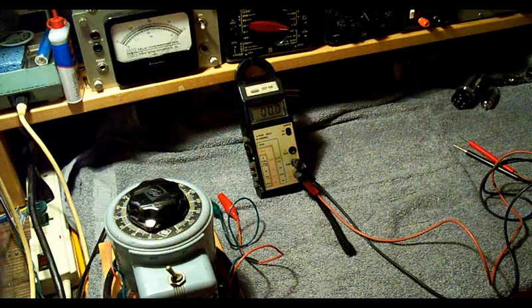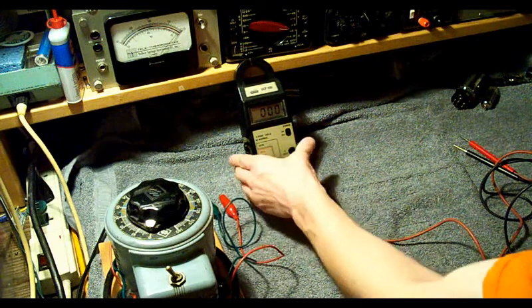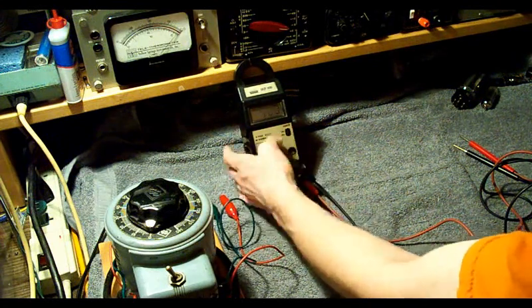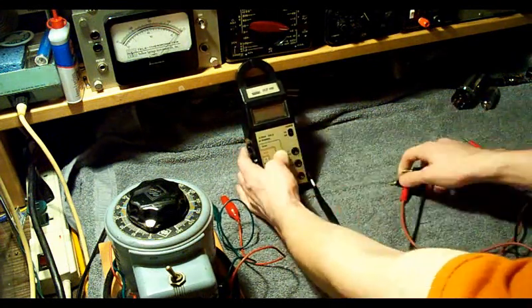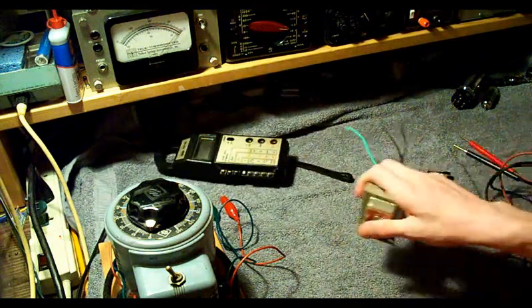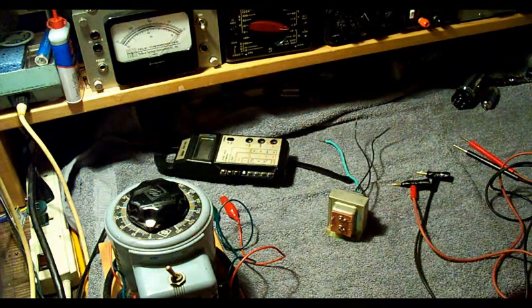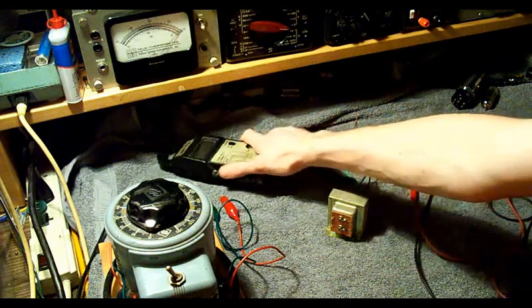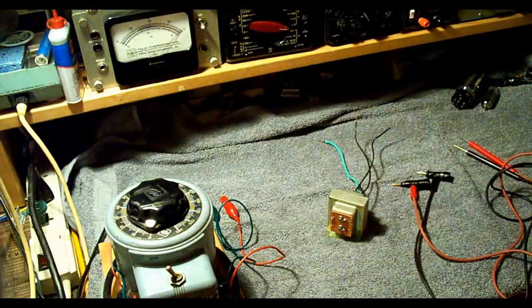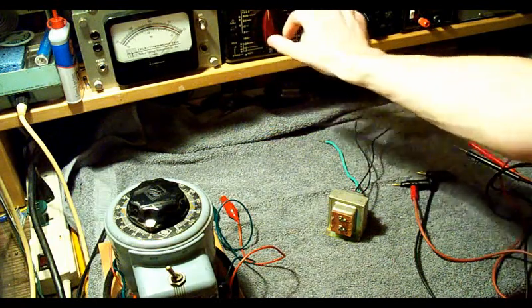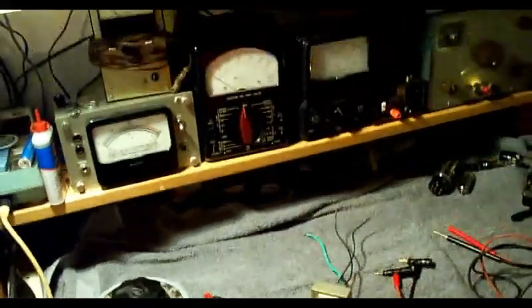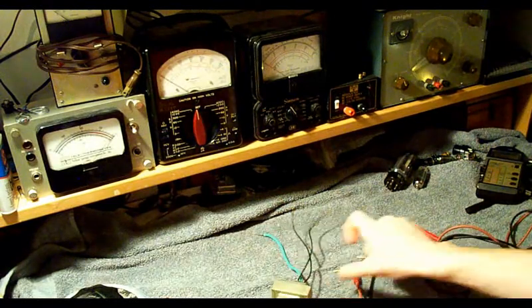Now, that was just a short video that I wanted to make showing why it's always important to check that, because like I said, the dangerous part about it is that it did not trip a breaker. You could have had this hooked up to a power supply. Nothing would have ever detected it was wrong. And as soon as you went to go touch those output terminals, you would get a good zap. And if you were to go ahead and ring your doorbell, it would immediately probably fry the whole doorbell circuit, the solenoids for the bells and probably the button too. So right there is a very good reason why it's always important to check these things, okay?